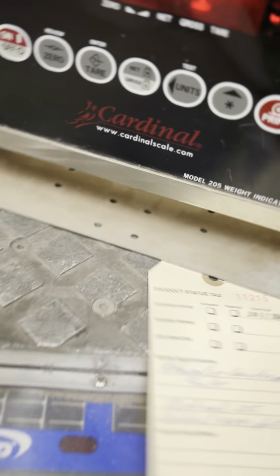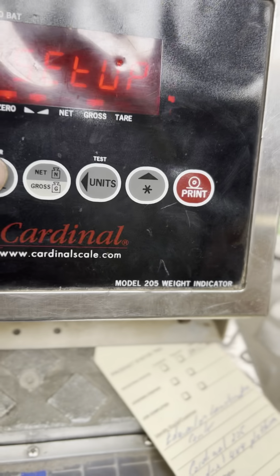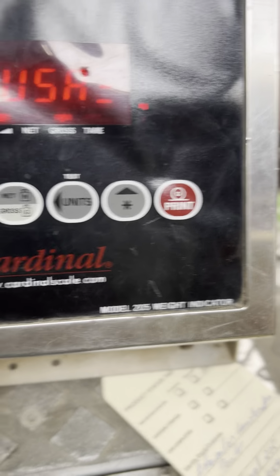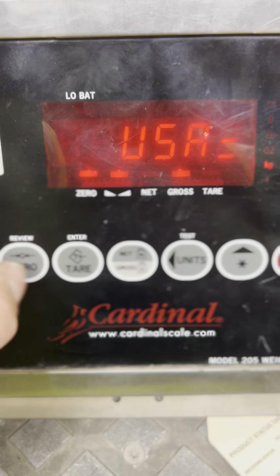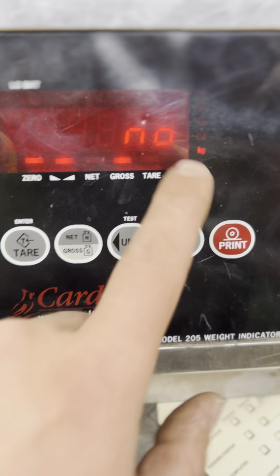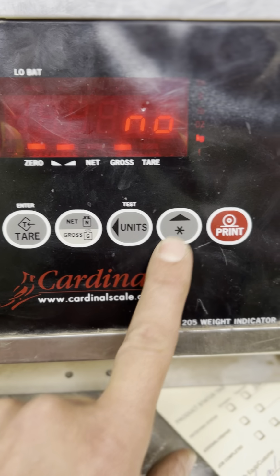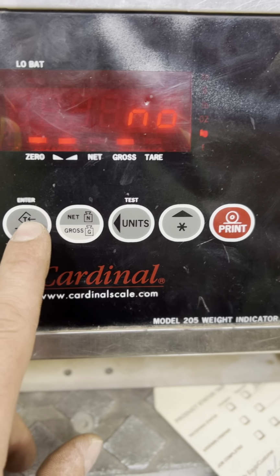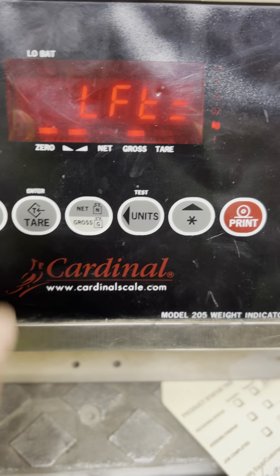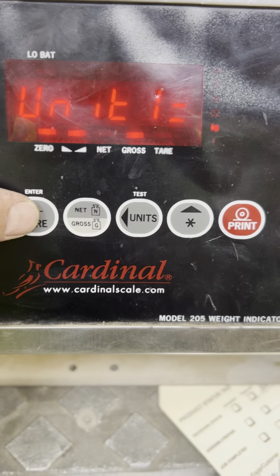We push the button inside with the screwdriver and now we are in the setup mode. Now we press Tare button. We can see USA. We press Tare button, it says no. We can change it to yes, but we in Canada don't need USA. So we press Tare. Legal for trade, yes.